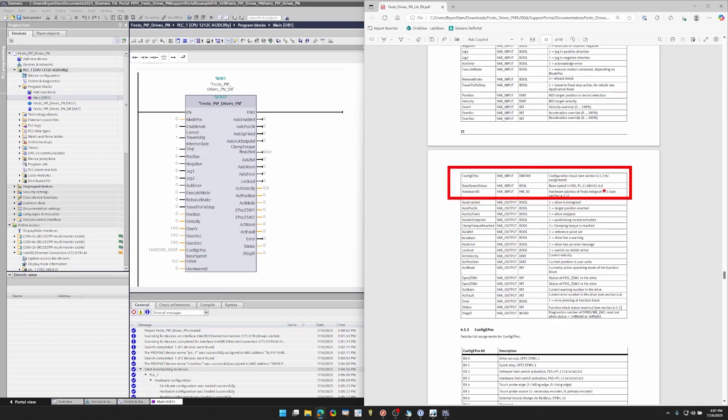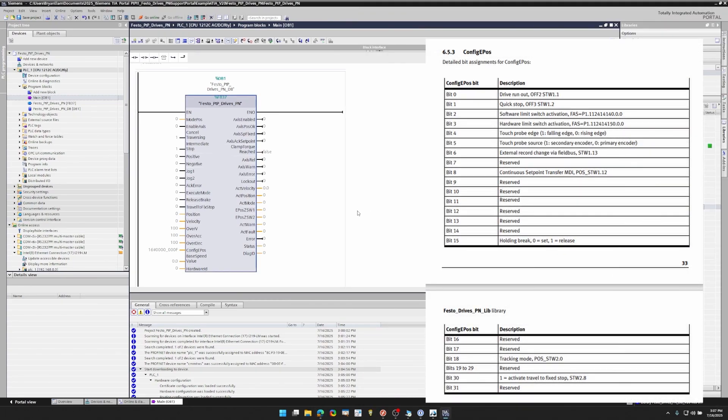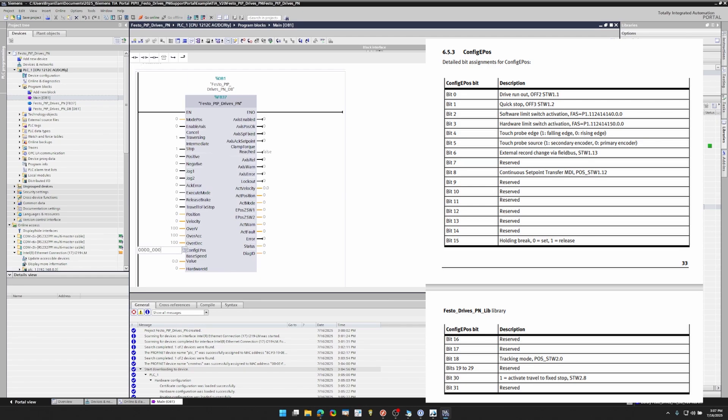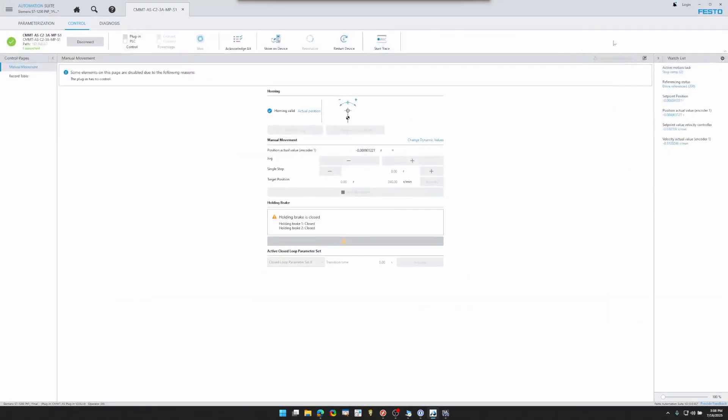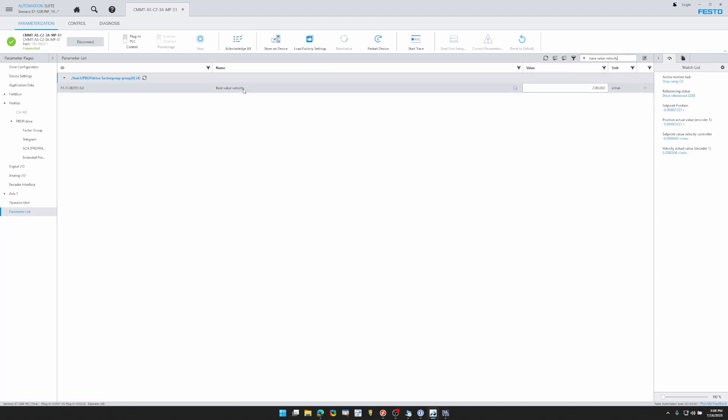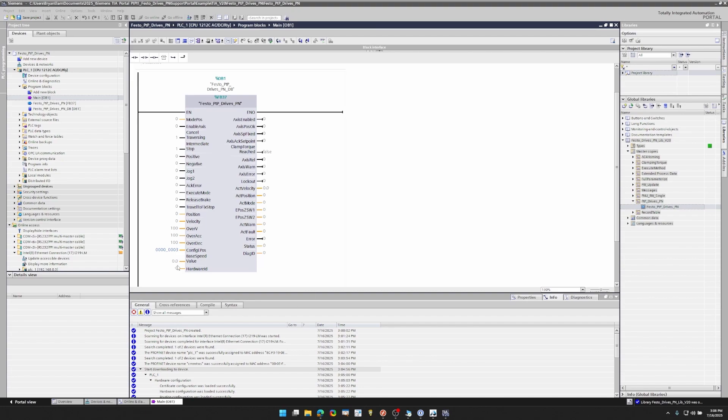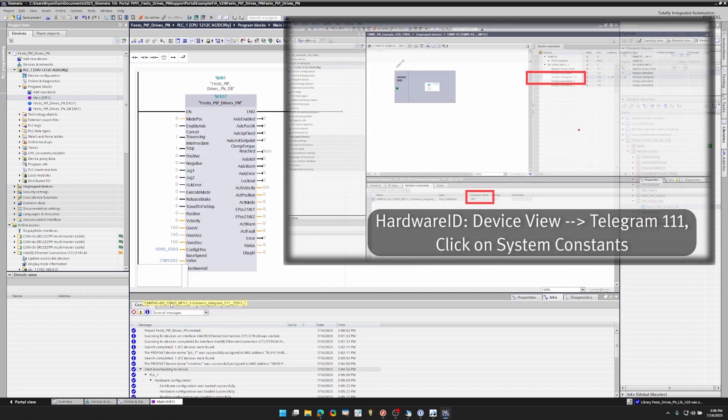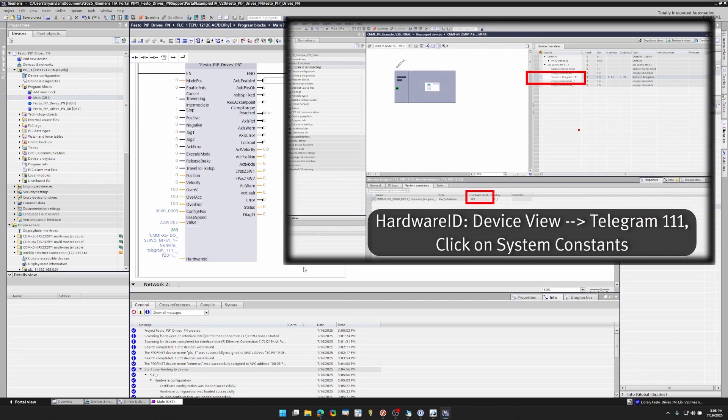Now these three parameters are not set up yet and we need to set them up. Otherwise, the function block won't work correctly. So let's do that now. The first one is ConfigEPos and I'm going to set it up with 0000_0003. And that's going to allow me to run the function block with no software limits and no hardware limits on the servo controller. You will have to look at the app note and see what bits you want high and what bits you want low and set that. The next one is base speed value. And this is directly output from Festo Automation Suite. You can go to the parameter list base value velocity and copy that value and paste that right into the function block. That allows the velocity to scale properly. Then last but not least, the hardware ID. You're going to want to select that telegram 111.